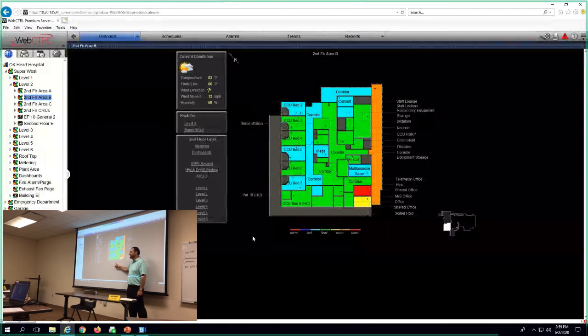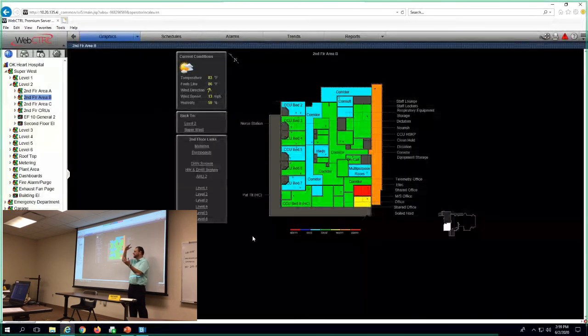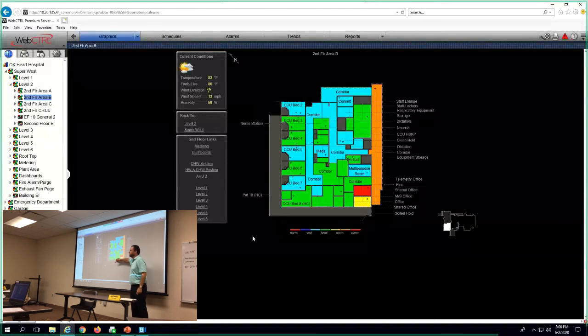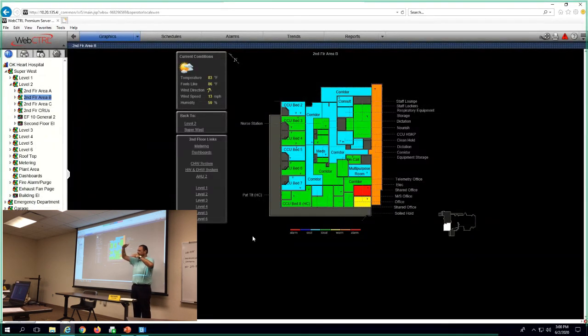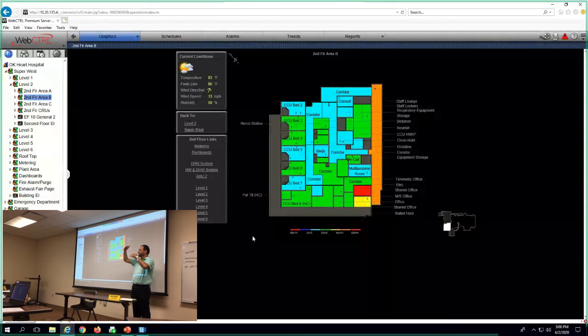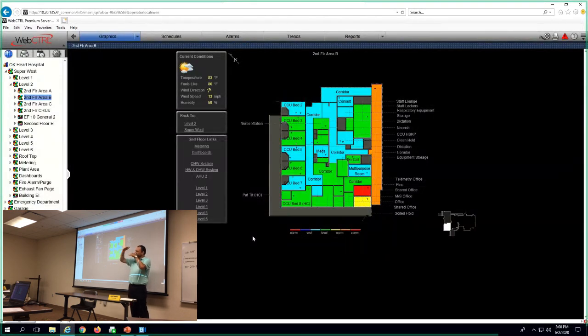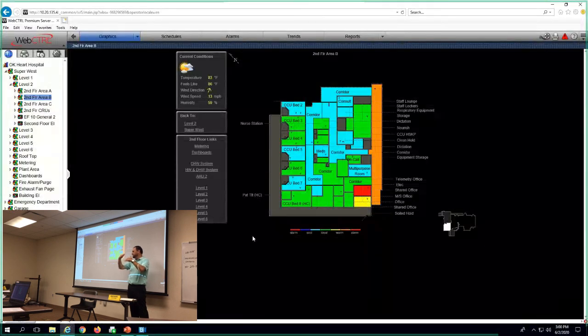If the temperature in the space is anywhere between the heating and cooling set point, let's throw some numbers in there. Let's say our cooling set point is 72 and our heating set point is 70. If the space temperature is 71 degrees or 71 and a half or 70.5, the space is going to show up green. All these spaces that are green are in between the heating and cooling set point, in what you've probably heard called the dead band. So there's a dead band between heating and cooling, right?